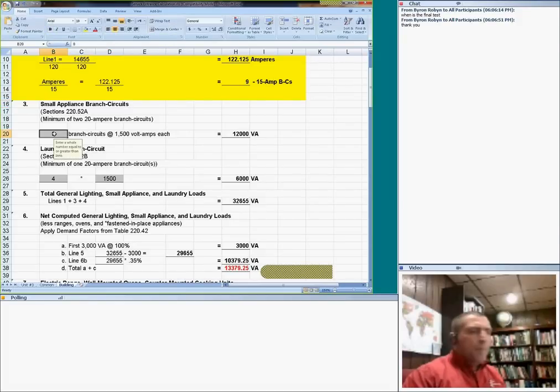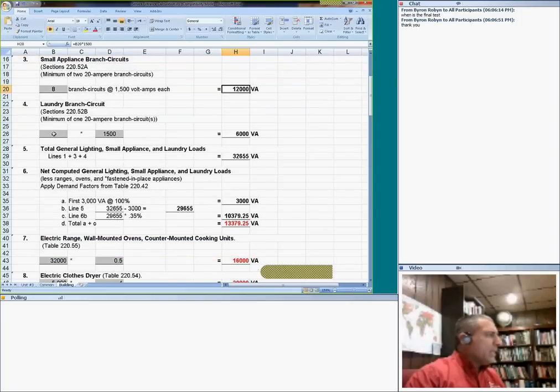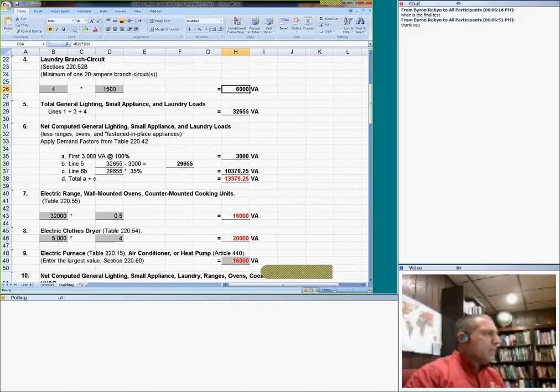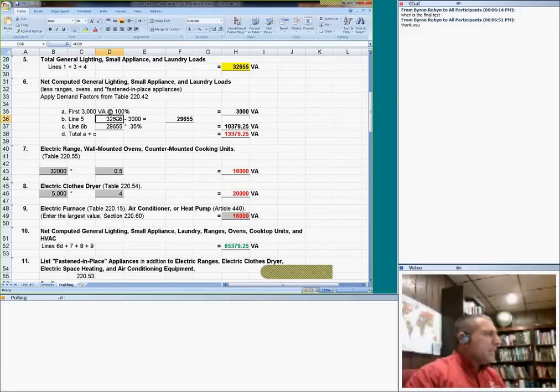This is an apartment building with 4 apartments. So I need 8. Why 8? Because 2 times 4 is 8. So this is for the kitchen small appliances. I need 4 laundry circuits because I have 4 apartments in this building, times 1,500, that'll get you 6,000. Then you add them up. Can you see that, where you add them up here? You add them up, and then you apply the demand factor. Can you guys see that? How you take this minus this, gives you this amount. The first 3,000, leave them alone. Anything higher than 3,000, cut it by 35%. So that's how anything higher than 3,000 gets cut by 35%.